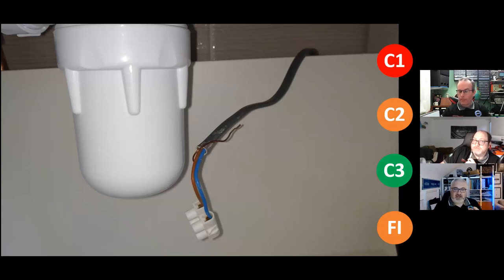Every story I've heard around these sorts of cables is, oh, the builder said he'd come back, or the electrician said he'd come back. There's a certificate. He sent an email. He forgot about it. So where are we with this? C2, C1? I'm going to go C1 just because it's under a cupboard and a small child could open it.